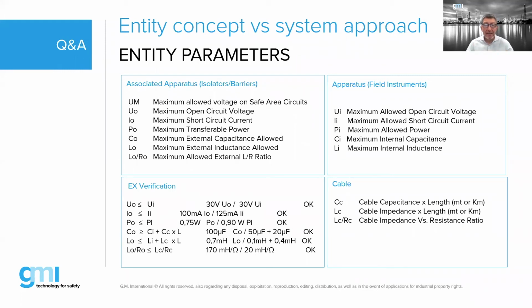But at the same time, the associated apparatus, the apparatus in the field, so your transmitter, is certified to be installed in a certain location within a given parameter. So basically, if it says the Ui of the transmitter is, say, 30 volt, it means that transmitter has been tested and certified to operate at a maximum of 30 volt. So what the barrier is there for is to guarantee you don't give it more than 30 volt. And this is true for current, capacitance, inductance. So it can get complicated.